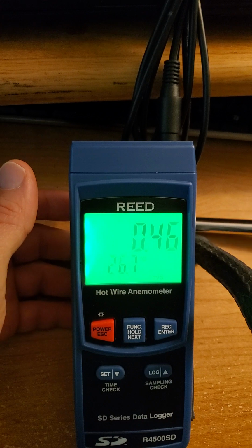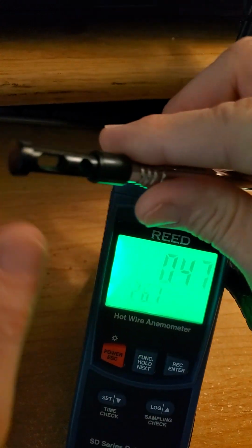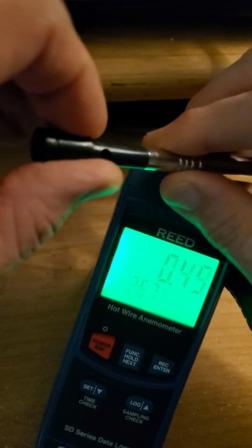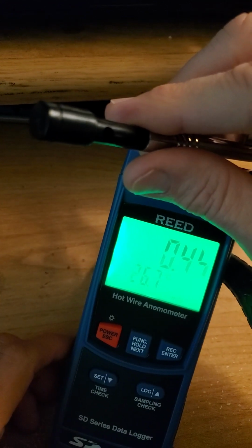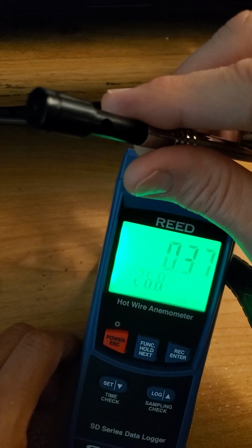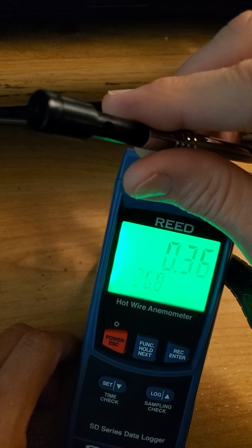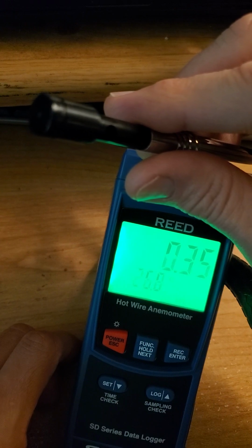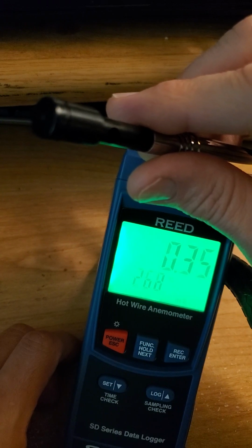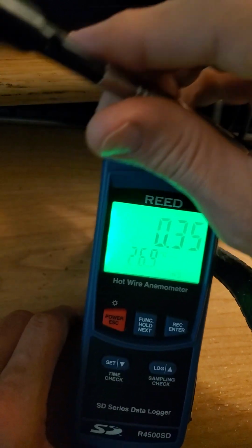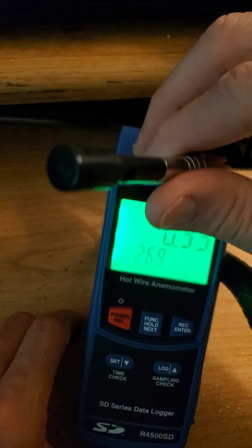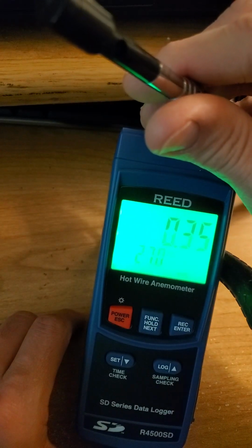So there's no wind going through, and I'll demonstrate by closing it that even with this closed, it does drop, but it doesn't show 0, which makes no sense whatsoever. This should be sensitive enough to register that the device is closed, and thus there's no airflow.